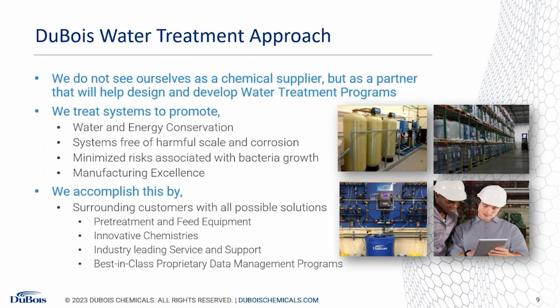Water treatment's become a very data driven industry. A couple reasons for this. Number one, 10 years ago, 15 years ago, you only got service when your sales rep was on site. So what happened if he left on a Tuesday and wasn't coming back for 2 weeks and a pump lost its prime? You might not feed chemistry for 2 weeks and no one would know. Now with online data management, we can get alarms that tell us right away.